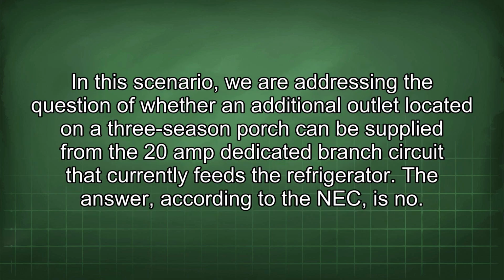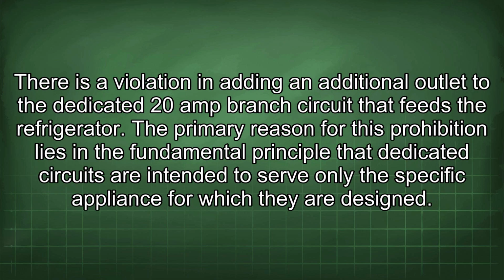In this scenario, we are addressing the question of whether an additional outlet located on a 3-season porch can be supplied from the 20-amp dedicated branch circuit that currently feeds the refrigerator. The answer, according to the NEC, is no. There is a violation in adding an additional outlet to the dedicated 20-amp branch circuit that feeds the refrigerator.